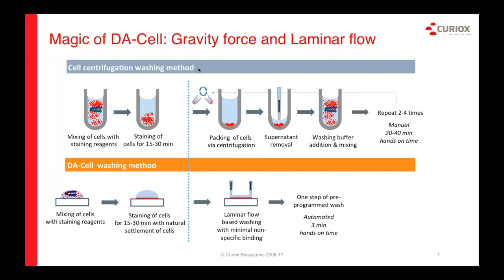The retention of beads and cells on the plate is based on well-characterized science. We use gravity and laminar flow — very well-known forces in nature. The secret is the use of these two forces on an almost flat, wall-less plate. The cells are mixed and settled on a plate by gravity, taking about 20 minutes, usually during standard incubation periods in a staining protocol. Once settled, the action of dispensing and aspiration above the cells doesn't disturb them. The wash solution forms laminar flow during dispensing and aspiration, minimizing turbulence. The velocity of the fluid becomes zero at the surface of the plate, so cells at the very bottom are not subjected to fast flow rates. Washing happens by diffusion rather than turbulence — this is how we wash cells without losing them.